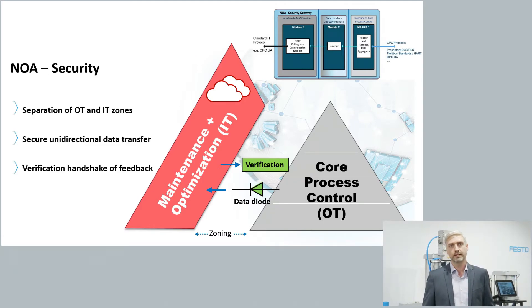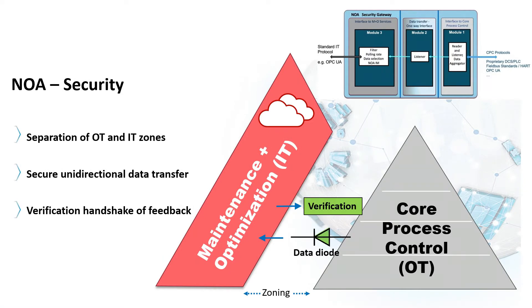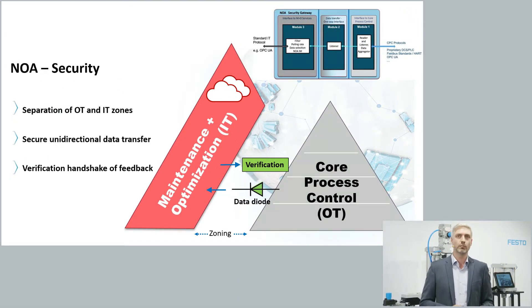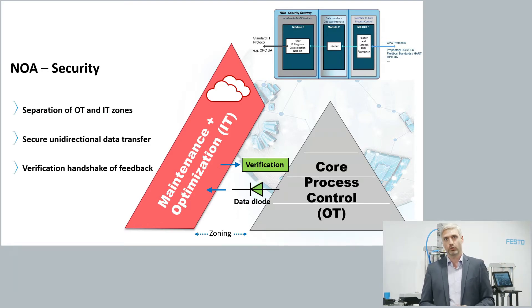On security concepts: one key aspect is the separation of core process control from the maintenance and optimization domain, as mentioned earlier. To make the zoning work, a barrier must be implemented between the two domains. Any communication path between them must be specifically secured. The main path — the readout of core process control data — is handled via what the working group calls a NOA security gateway, also commonly called a data diode: it enforces unidirectional communication, only outward from the field into the maintenance and optimization domain, with no feedback from the IT domain into core process control.